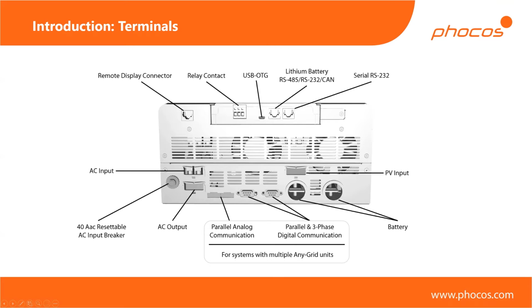Then on the bottom, we have all of the power connections and some more interfacing. We have the AC input on the top here and the AC output on the bottom. We have a resettable 40 amp AC fuse or input breaker here. So again, this is resettable. If it pops out, you can just pop it back in. Then we have the parallel communication interface right here, because as you'll see later in the extensibility section, we can use that to interface with multiple units.